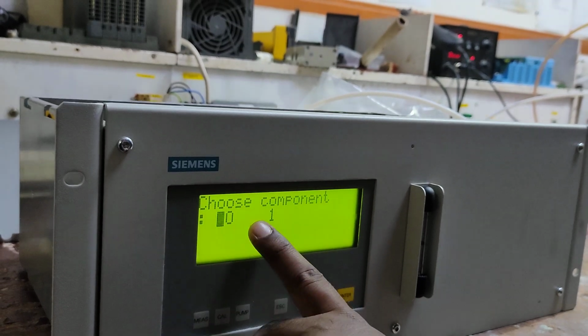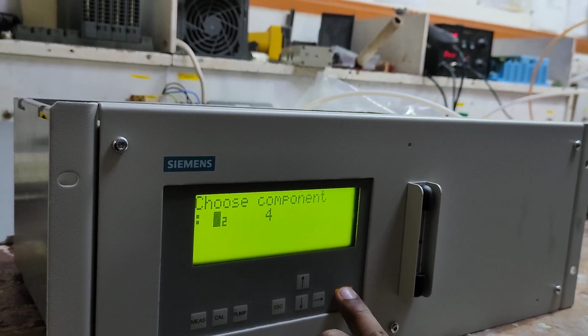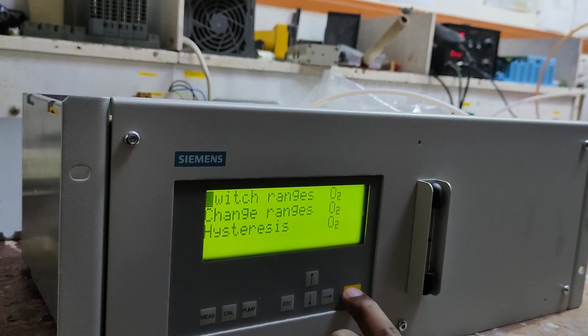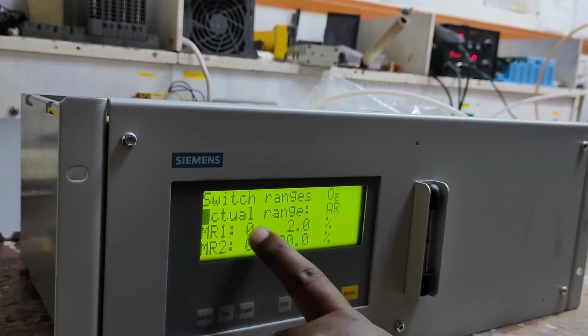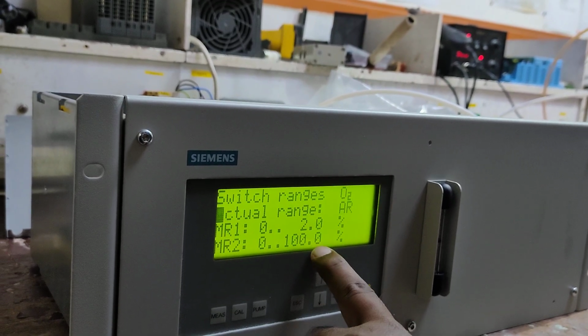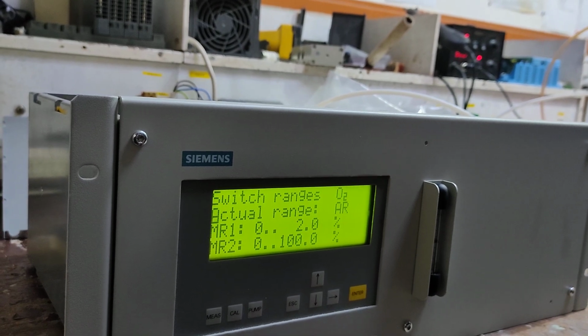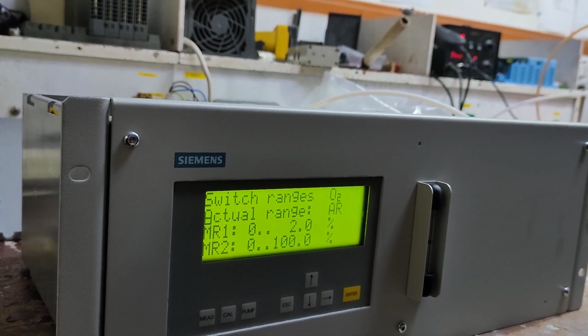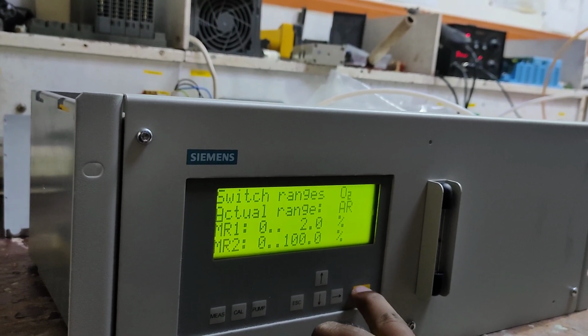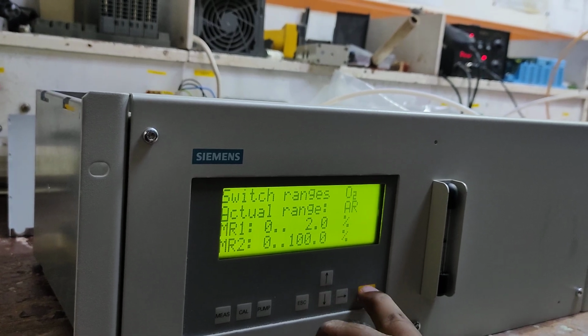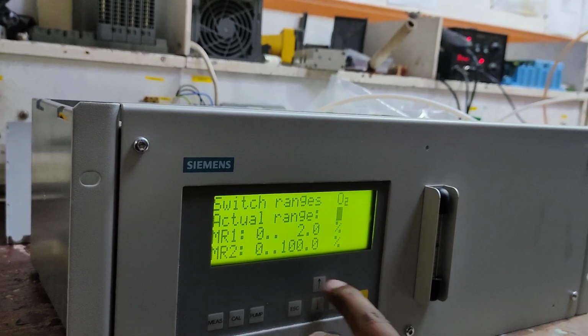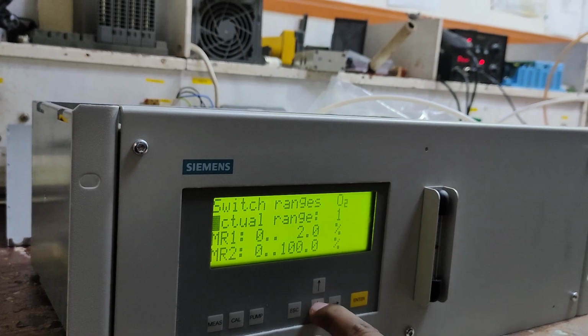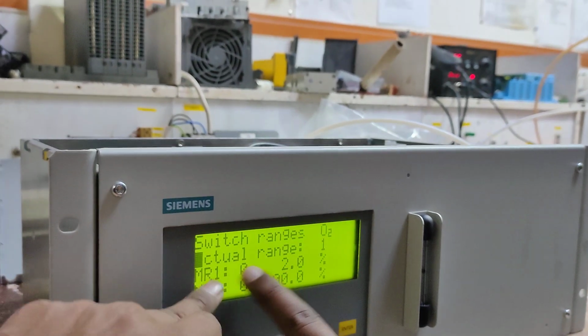Now we did it for CO. Now let's check O2. For O2 we have a switch range. The first range is 0 to 2%, the second range is 0 to 100%. How much is the range for O2 in the DCS? Actually, we have 0 to 10 only. So you can change it here. We can put one only. This one also we can edit.